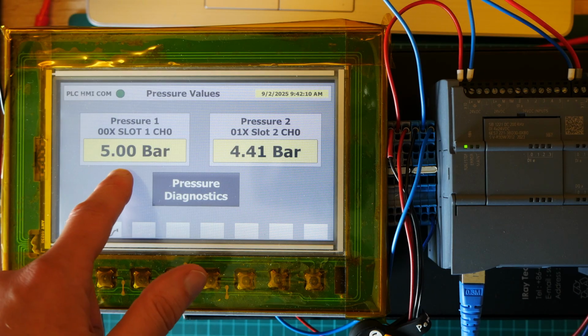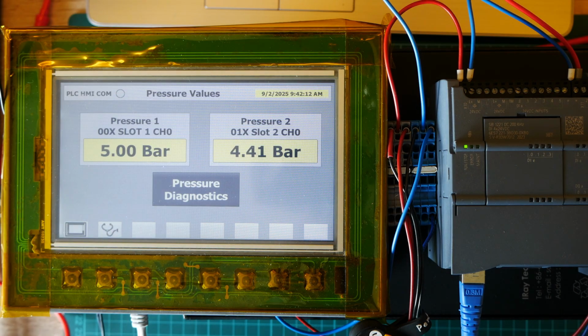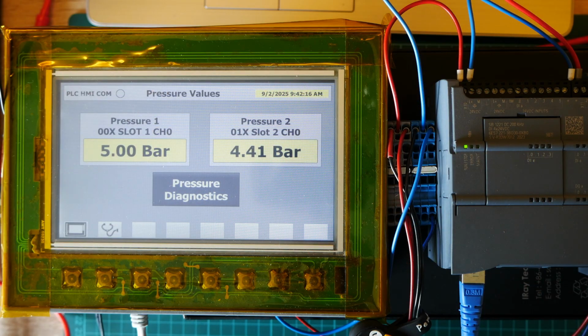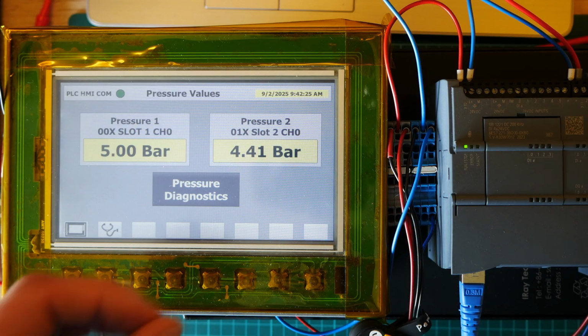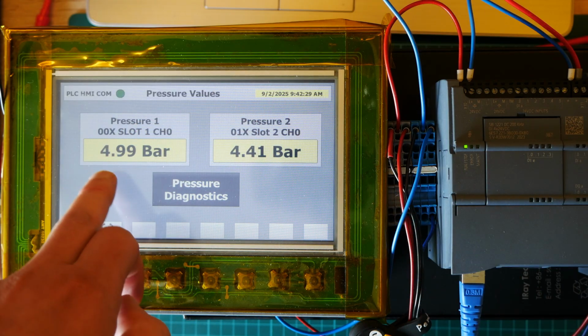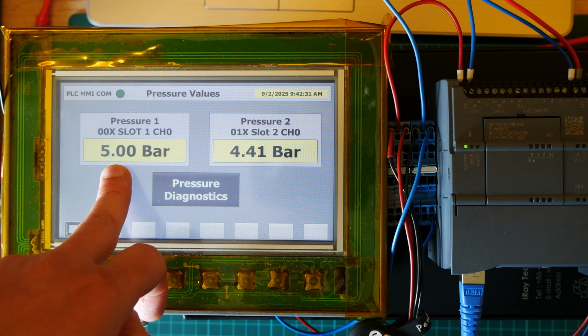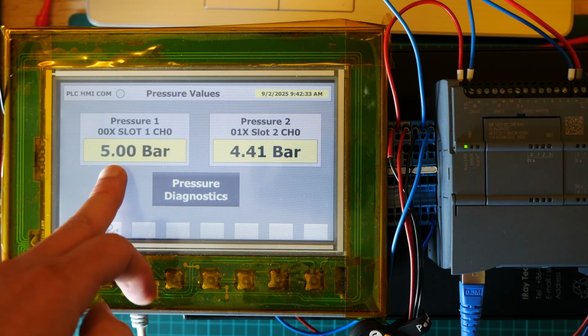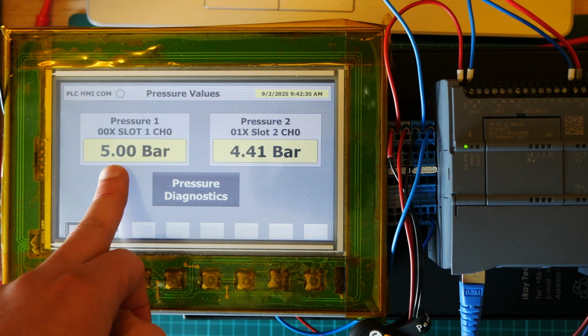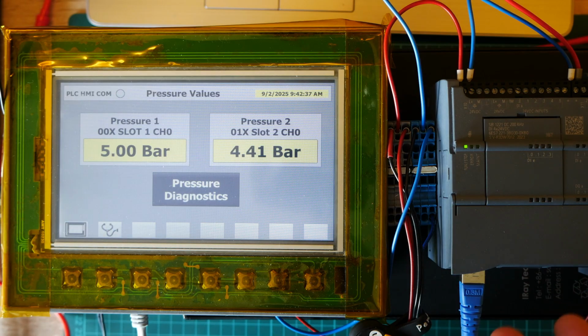He goes to maintenance and says to the electrician, okay, the valve physically is closed, the pipe is disconnected, the pump is, let's say, turned off, and I see on the physical manometer it shows 0 pressure, but on the HMI I see 5 bars. So something is not okay. And then what to do for the electrician? How to solve this issue?